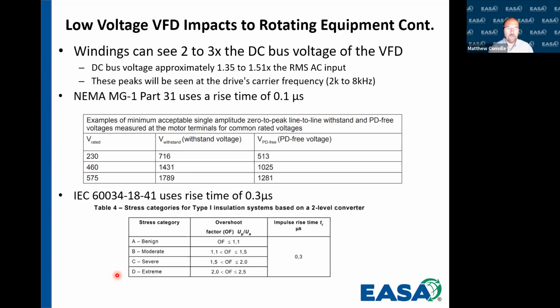So if we order an IEC machine and we say we just want it to be inverter rated, we could have a stress category of A, benign, and it would be relatively inexpensive material that's used in it, because we're assuming that the peak voltage is only going to be 110% of what the actual voltage is. And we're seeing that if we don't use any filtering, it's going to be 2 to 3 times. So if we're 2 to 3 times, we really need to be in this C and D category. So the major takeaway here is that if we're going to specify an IEC machine, we need to make sure that we're using the appropriate stress category.